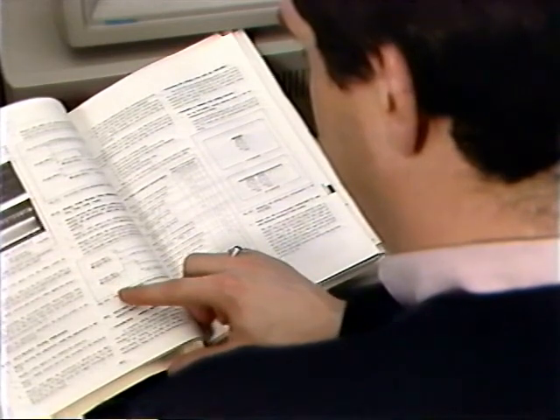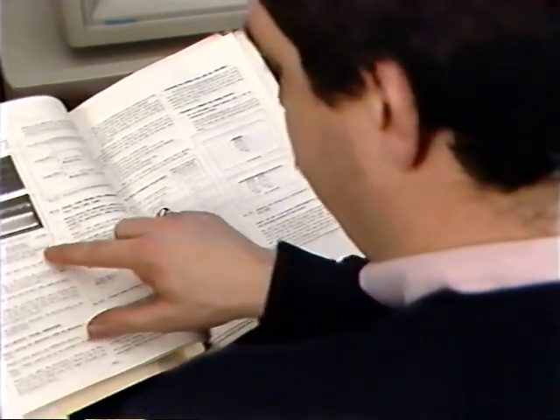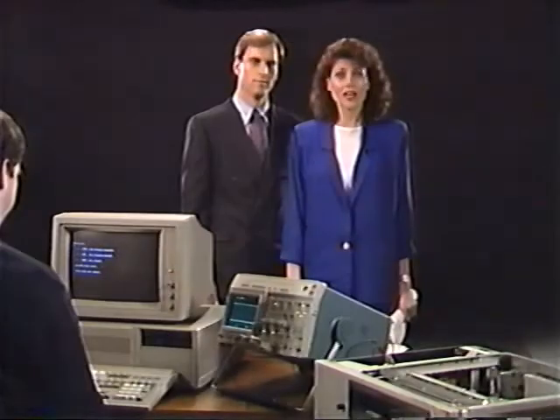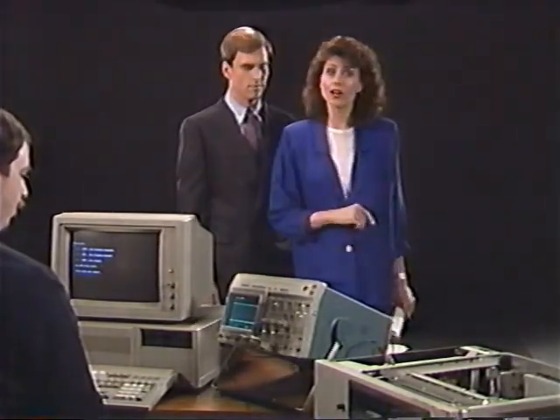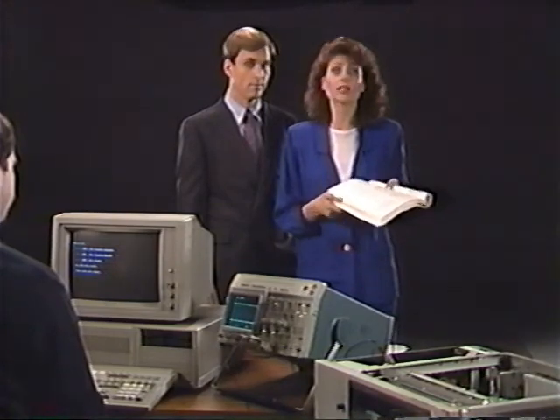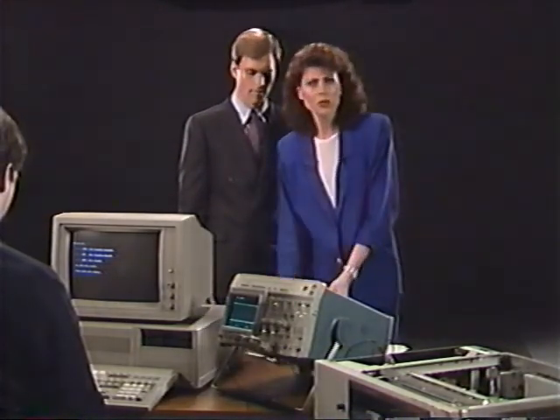An engineer creates an EZtech procedure as a series of steps using the EZtest program generator module. The calibration procedure for this VTR occupies 5 pages in the service manual and requires 50 steps. Manually, this procedure could take 3 hours or more to do. To automate it, the engineer uses the EZtest program generator to enter each step. Once the scope's front panel setups are stored, the engineer enters operator prompts, measurement limits, branching directions, and data output locations. This approach makes it easy for an engineer recently trained on a specific instrument to transfer new knowledge into an EZtech procedure.